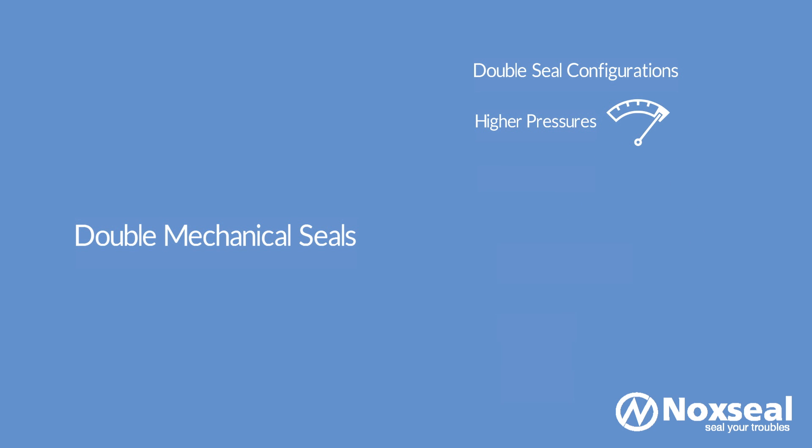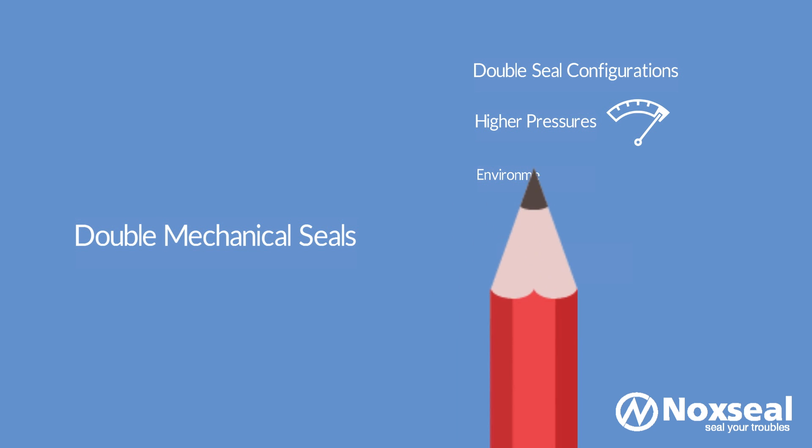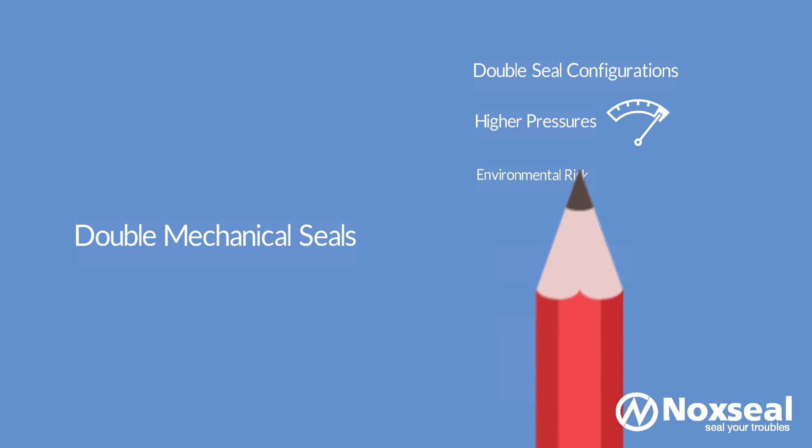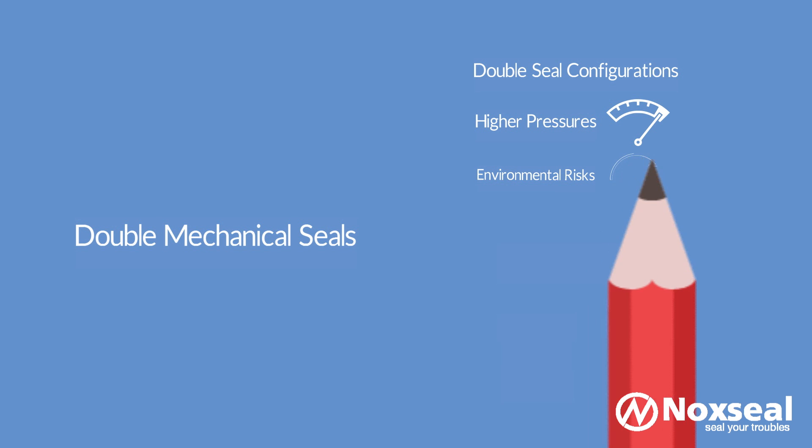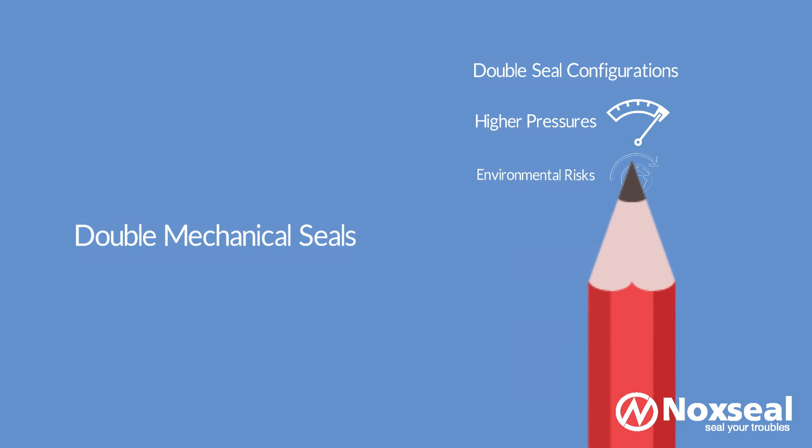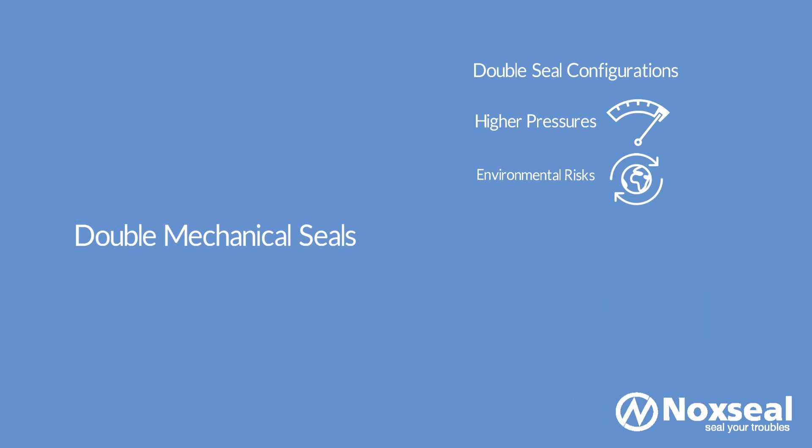In a double seal, two seals are oriented in opposite directions and there is a pressurized barrier liquid that is circulated in the cavity between the two seals. The barrier liquid is circulated at a higher pressure than that of the process fluid so that if the primary seal fails, the barrier liquid will leak into the process instead of the hazardous pump fluid escaping into the atmosphere.